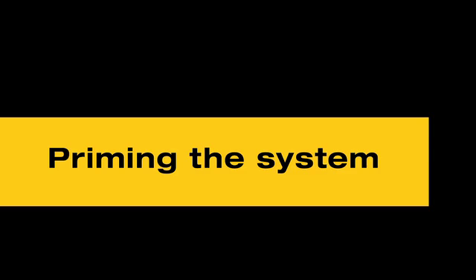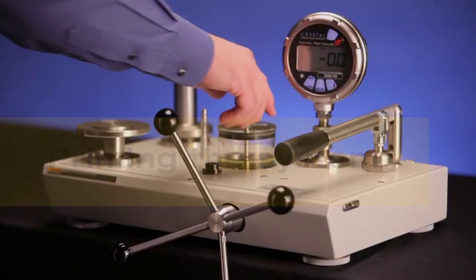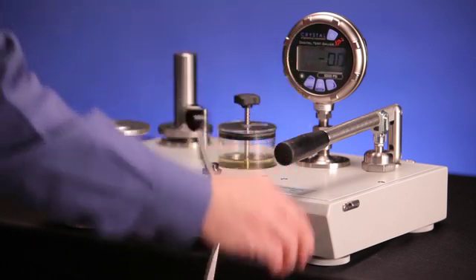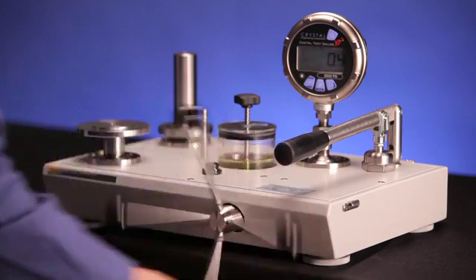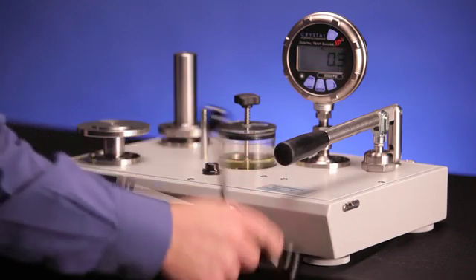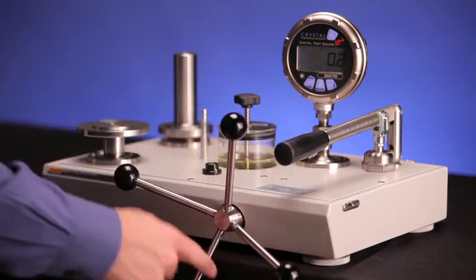As with all hydraulic systems, the air must be removed from the system. The priming process for the P3100 series is simple and efficient. Open the reservoir valve one turn counterclockwise and turn the variable volume fully in. Pump the priming pump two times.